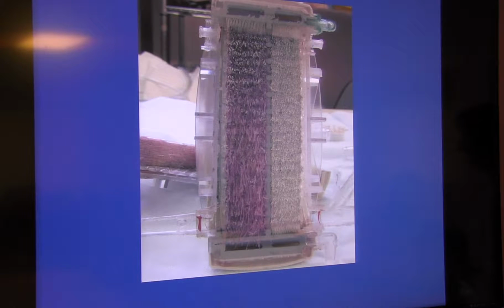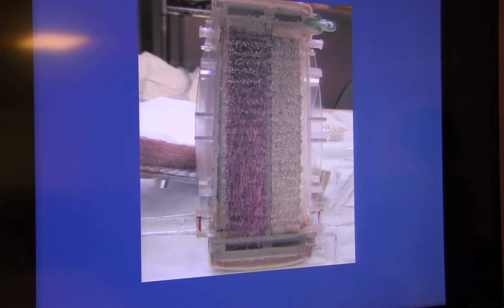2.8 on the blue. I just got that. Yeah, that's what I thought. So the pediatric oxygenator is rated to flow at 2.8 liters, but we use 15 kilos as our cut point between when we switch from our neonatal circuit up to our adult circuit, because we want to leave some more forgiveness in the system than that. I was thinking 5.7. What did you say the max was? 2.8, but we really switch around 15 kilos.